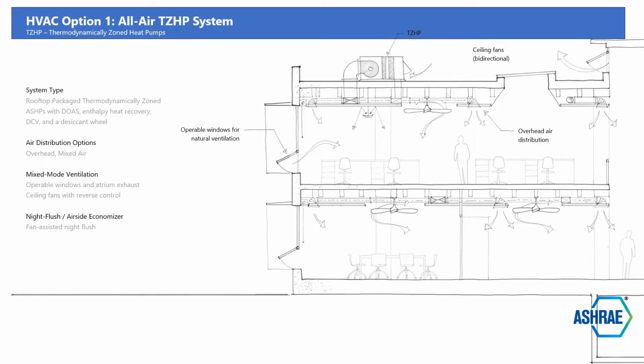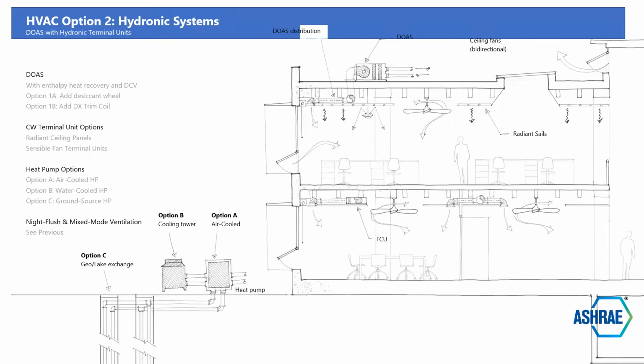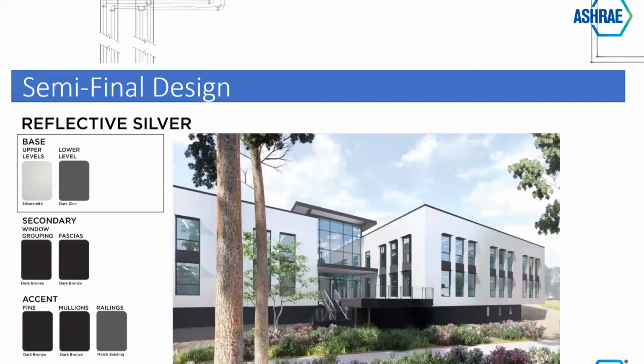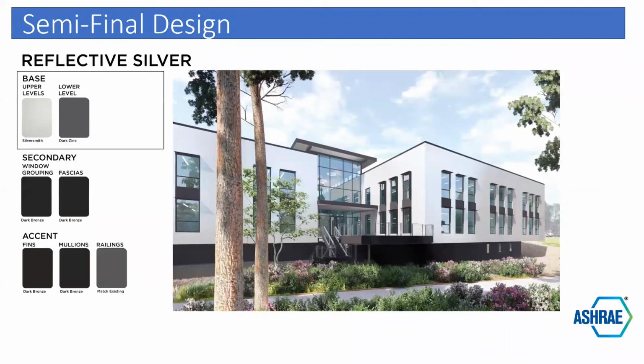And so in this one here, you can see that we have some air coming in. That's with the all air system. But we went with the HVAC option 2 hydronic system. So it's with enthalpy heat recovery, desiccant heat wheel, chilled water terminal unit options, radiant ceiling panels, sensible fan terminal units in higher occupancy areas, air cooled heat pump. Water cooled heat pump was an option, but we didn't go for that. And we also evaluated ground source energy, but the number of wells put our costs above our budget.